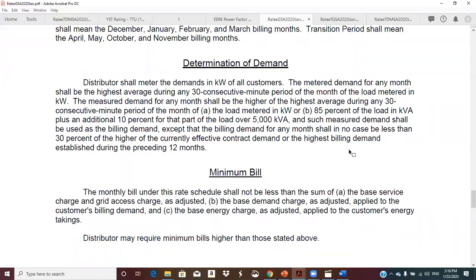So they'll either charge you for the metered demand or for 85% of the load in kVA, plus there's an extra 10% if you're drastically too large, though that usually doesn't come into effect—you don't see it very often, but they will do that calculation. If you're on this rate structure, though, you're probably not going to be above 5,000 kVA.